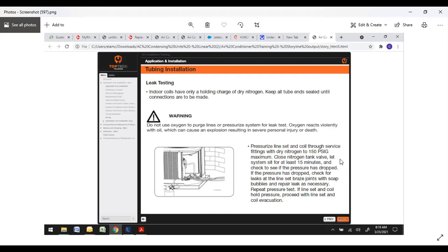Close your nitrogen tank. Let your system sit for at least 15 minutes. Make sure your pressure is not dropping. If it starts to drop, check your hoses, check your connections, do some leak testing with soap bubbles. If you do find a leak, make the repair and then repeat the process.